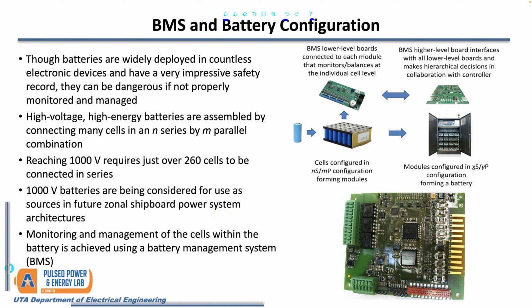So, BMSs and battery configuration. Batteries are typically configured with a bunch of smaller cells in an N series and M parallel configuration, forming a module. Those modules are then connected in an X series and Y parallel configuration to increase voltage and current capacity, and each module interfaces with its own BMS card. So you can get batteries where the cells are only 3.3 volts, but if you put about 270 in series, you'll get an end result of about 1,000 volts.